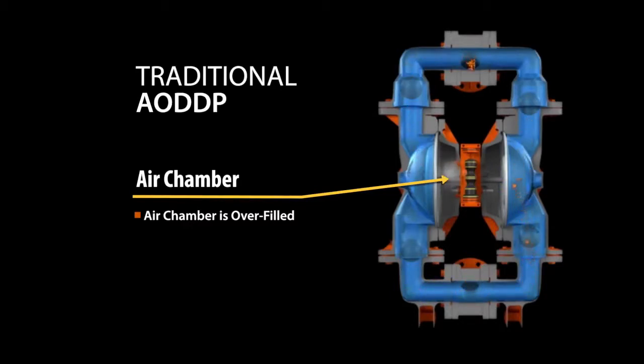Once the shaft and diaphragms have reached the end of their stroke, a mechanical mechanism triggers the end of the stroke, finally shutting off the air supply to that air chamber, signaling the air valve to shift and dump any excess air left in the filling air chamber.